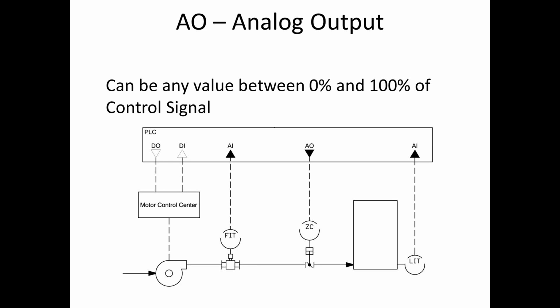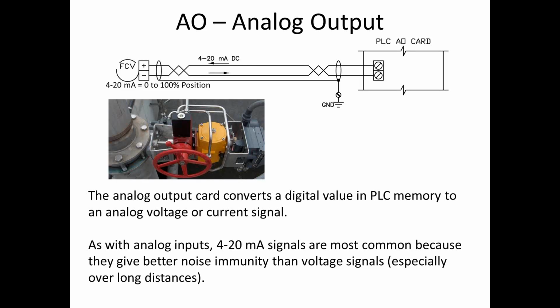And then that level indicating transmitter at the very right-hand side, at the very end there, sends an analog input to the PLC and gives the PLC an indication of how full it is. When it gets to a certain level, it sends a digital output to the motor control center, which actually shuts the pump off. So that's how those signals actually work. And I'm going to skip over that because we've talked about analog outputs and 4 to 20s.